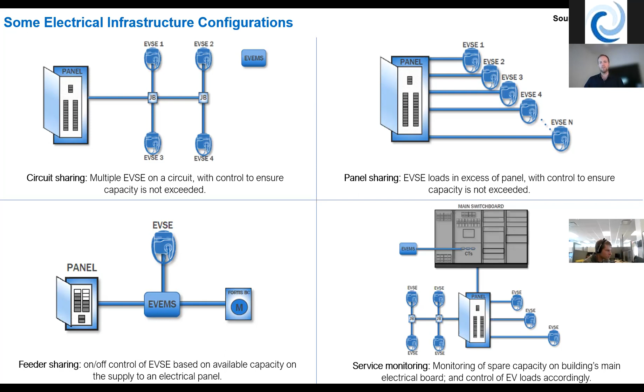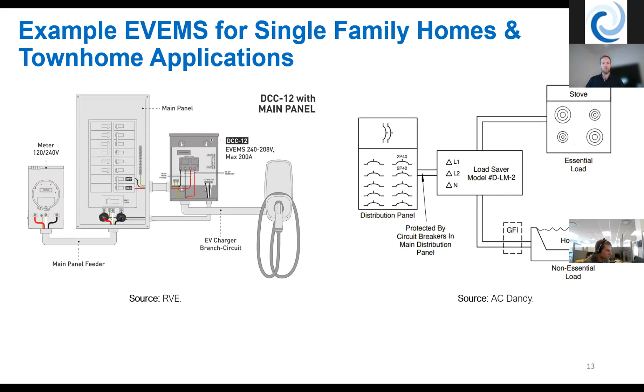I'll also note, as I did previously with feeder sharing, that these are examples of systems for single family homes and townhome applications in particular, where, again, you'd be monitoring the capacity of the main panel and providing charging for the EV charger whenever the capacity of the panel isn't being approached. Or you could just have two major loads. Let's say instead of a hot tub, this would be your EV charging. So if your stove or your dryer is on, your EV won't be charging. But whenever those things aren't in use, your EV can be charging. That'll provide a perfectly adequate quality of service. So these are some examples of different EV energy management configurations that can be used.